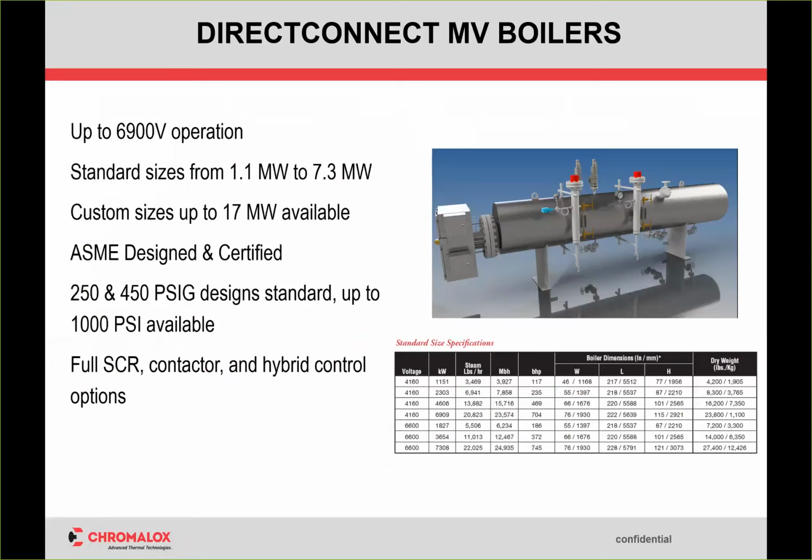It's probably not horribly large, because that's another point to these medium voltage boilers I want everyone to take away from this. When you're talking to customers, when you're reviewing and explaining to them that we have this technology available, we have the sizing, these boilers are going to be a third, a fourth, I'm being conservative here, the size of the gas-fired equivalent. That's huge. That's less real estate. That's easier to monitor. There's a lot of advantages here beyond what we put on paper that we need to illustrate to our customer. And I think that is a big key component right there of just the physical size. These are significantly smaller.